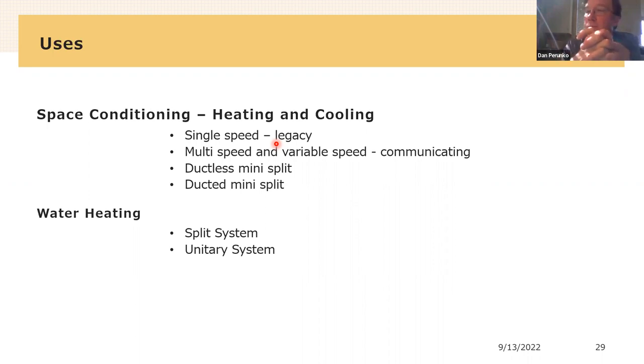Then we have multi-speed and variable speed communicating systems. That picture where we saw the coil that was only partially frosted up, that's a variable speed communicating system. And it has much, much higher efficiency because it has this operational range that goes down to maybe 30% of its total capacity up to its full capacity. So its electrical consumption can reduce to less than a third, it's not linear. A machine might be able to drop its electrical consumption down to about 300 watts, and then it could also ramp up to over 2000 watts, right? So there's this huge range of electrical consumption available, and we want the machine to only consume as much power as necessary in any given situation. And that's what the variable capacity and multi-speed communicating machines can do.